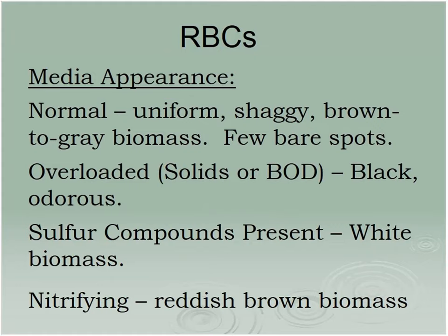If it's black and smelly, then we've overloaded the unit. You can also see somewhere you've got a white biomass on there. That's indicative of a couple of filamentous organisms over here that thrive on sulfur compounds. If we're nitrifying, we're going to see a reddish-brown biomass.